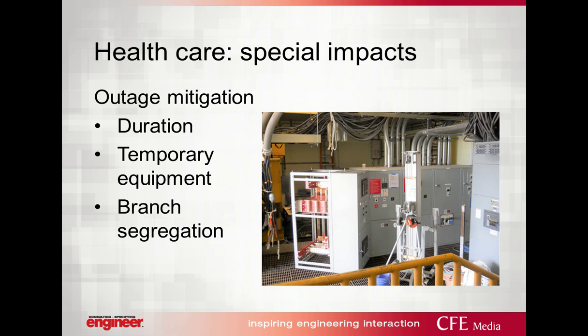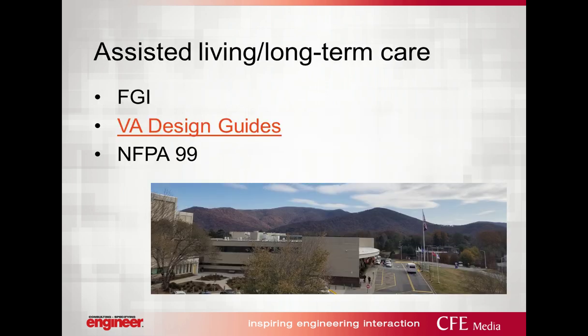And throughout many of your projects when you're remodeling, always take into consideration that if you want somebody to make a connection to a bus, they're going to have to shut it down. And if that means locking out the generators, then you don't have emergency power. That means you no longer meet the requirements of 517. So always take that into consideration as a special impact to healthcare, but something that also impacts the occupancy of other types.